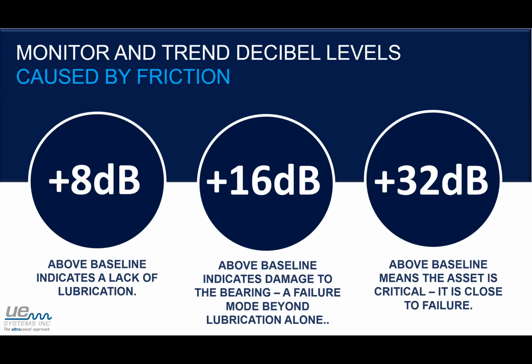So let's say we have a baseline of 10 decibels, just making that number up. When we see a change of 8 decibels, so the bearing is now reading 18 decibels, that's an indication that bearing requires lubrication. So when the OnTrack gets that information, it's going to send you that quantitative information: at this point in time, this bearing increased by this many decibels. But it's also going to give you that very prescriptive alert I've been talking about: this bearing requires lubrication.